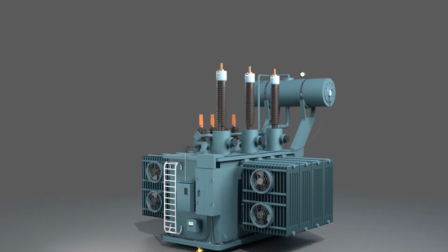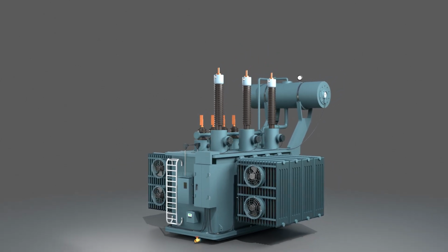The power transformer's cooling fans have stopped. Now, the cooling panel starts to heat up as the temperature rises. Then, the fans kick back on, spinning fast, and the cooling panel begins to cool down again. Back to normal, just like that.